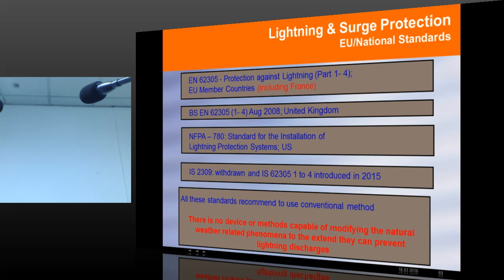So in Britain, BS EN 62305 is the standard, NFPA 780 for America, and in India, from last June onwards, IS 62305 is introduced, and all these standards recommend using the conventional method, Franklin rod or Faraday cage. This is the only method explained in the standard. There is no device or method capable of modifying the natural weather-related phenomena to the extent that they can prevent lightning discharge. This is the first heading of the standard. What it means is, lightning is a natural phenomenon, you cannot modify it or catch it. It will flow or it can hit anywhere. What is possible for us is to ensure that our properties are protected and people are protected.